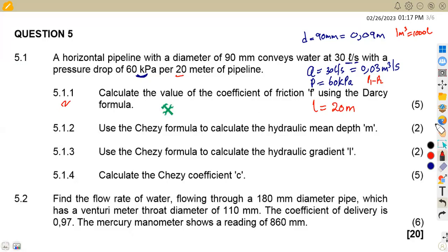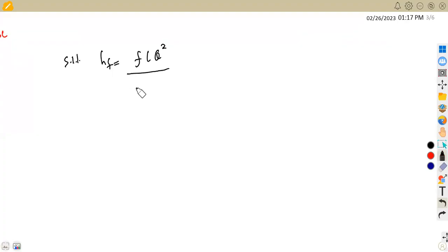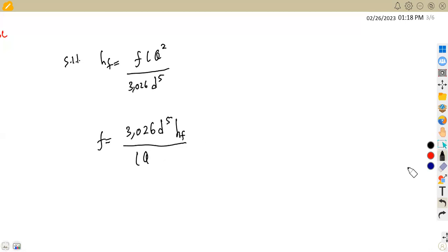To find F, we start from HF, where from the Darcy formula: HF = F·L·Q² / (3.026·D⁵). Transposing for F gives: F = 3.026·D⁵·HF / (L·Q²). We have everything except HF, so we need to calculate that first.